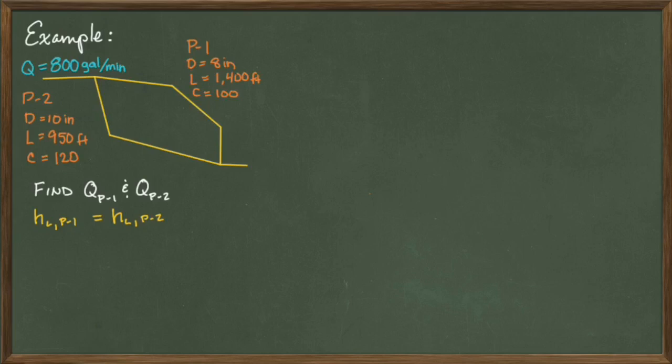First, we know that the head loss in pipe 1 is equal to the head loss in pipe 2. Also, we know that the flow rate in pipe 1 plus the flow rate in pipe 2 is equal to the original 800 gallon per minute flow rate entering the flow split.